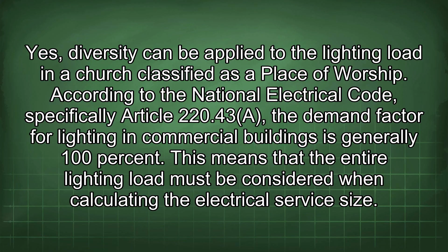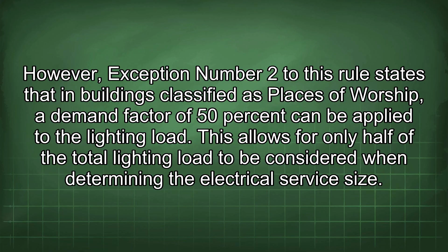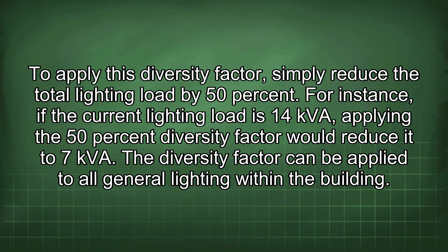However, exception number 2 to this rule states that in buildings classified as places of worship, a demand factor of 50% can be applied to the lighting load. This allows for only half of the total lighting load to be considered when determining the electrical service size. To apply this diversity factor, simply reduce the total lighting load by 50%. For instance, if the current lighting load is 14 kVA, applying the 50% diversity factor would reduce it to 7 kVA. The diversity factor can be applied to all general lighting within the building.